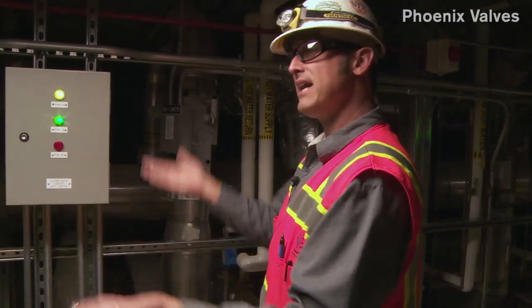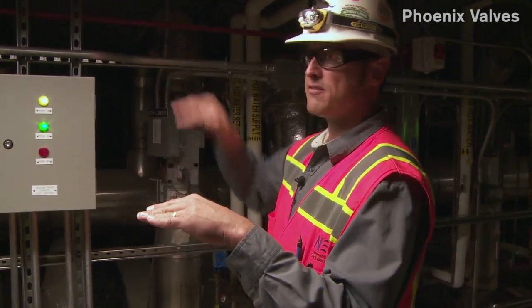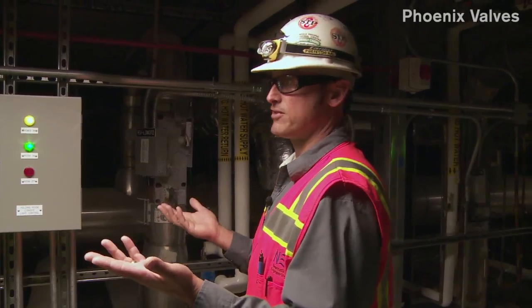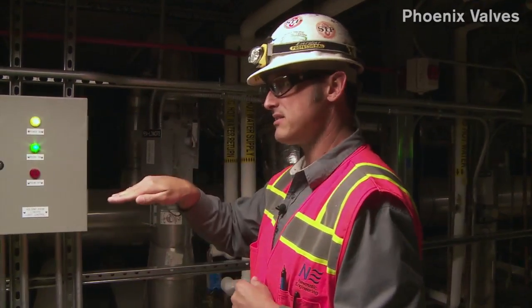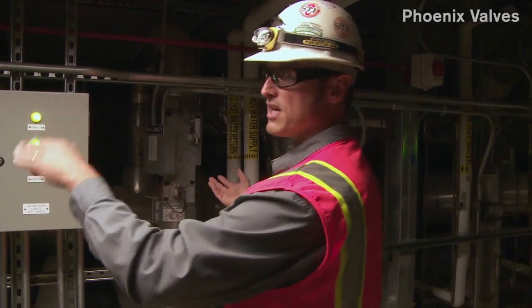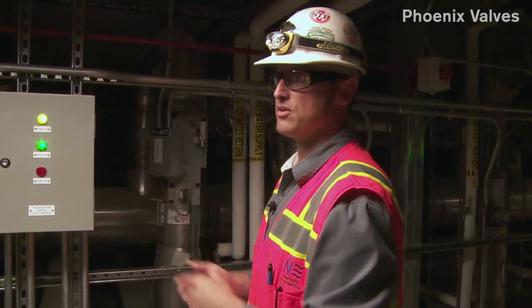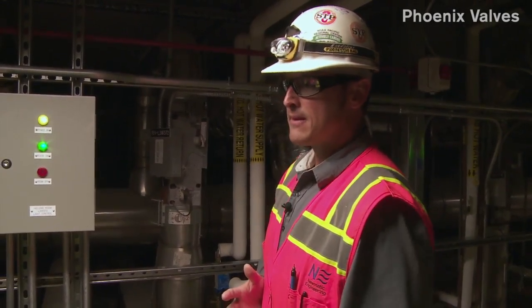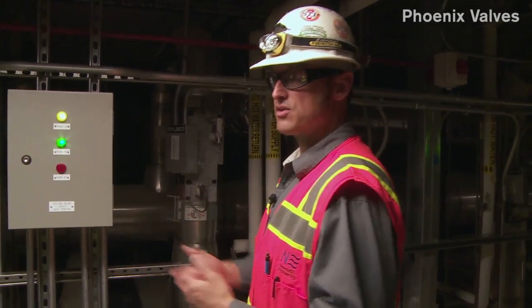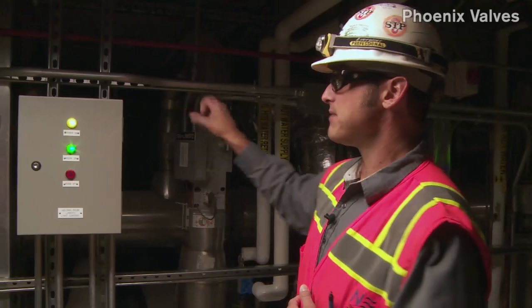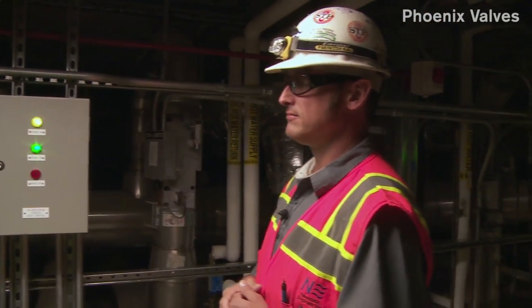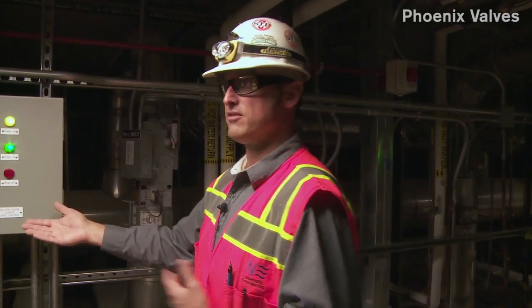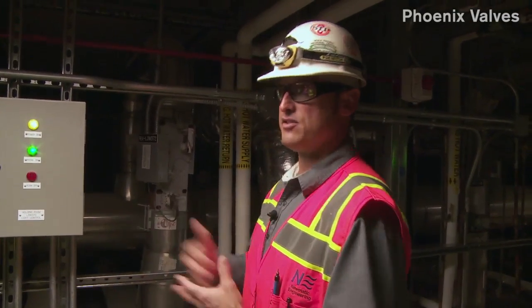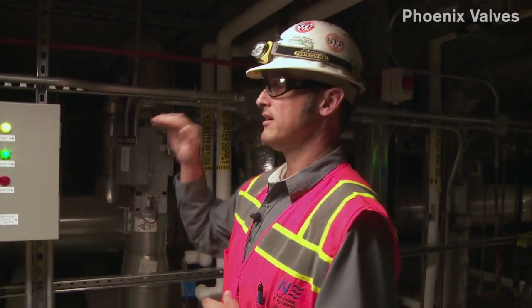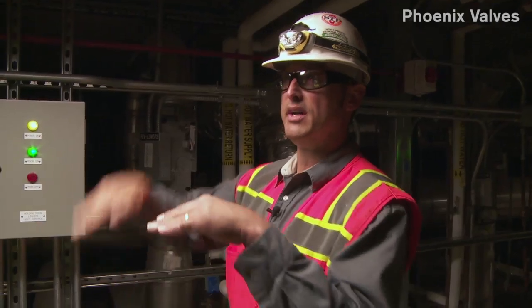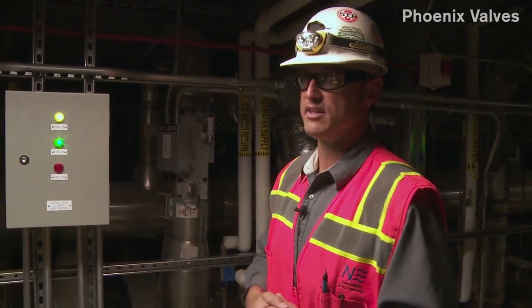In some cases, both supply and general exhaust move. Most of the cases, just one valve will move. In some of them, it's the general exhaust that moves up and down and the supply stays the same. In other cases, the general exhaust stays the same with the hood valve and the supply valve opens and closes. And again, the corridor valve responds to those switches also. It takes a total of all the feedbacks that we've programmed in. If you have so many rooms that are positive and so many that are negative, it's taking that math, and we've programmed the actual formulas in there to make sure that the supply and the exhaust for the corridor maintain what they need to for whatever polarity the rooms are doing.